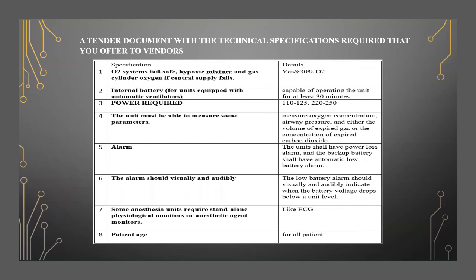A tender document with the technical specification required that you offer to vendors. This schedule shows the specifications required for the anesthesia machine and details. O2 system fail-safe, hypoxic mixture and gas cylinder oxygen if central supply fails. This details 30% O2. Internal battery capable of operating at least 30 minutes. Power required is 220, 250. The units must be able to measure some parameters like oxygen concentration, airway pressure, and either the volume of expired gas or the concentration of expired carbon dioxide.